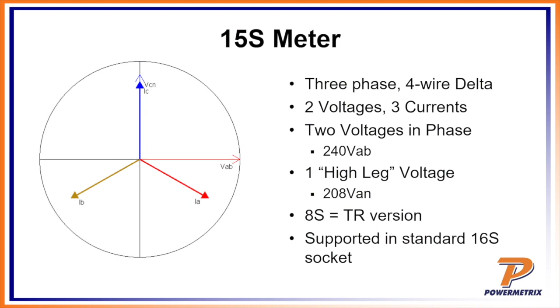If you're an older meter tech, you may remember the transformer-rated version, the 8S mechanical meter, that's kind of what it supported. But the nice thing is the 16S socket supports both meters, a 15 and a 16, which a lot of the meters actually say too, it'll say 16/15 right on there.